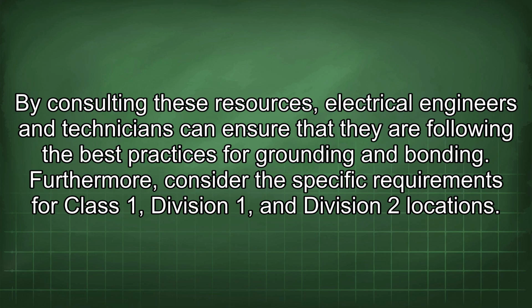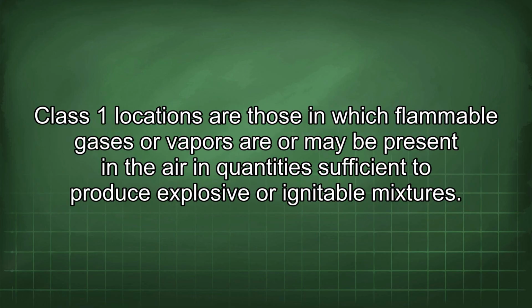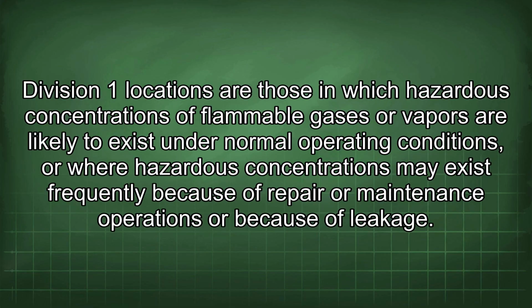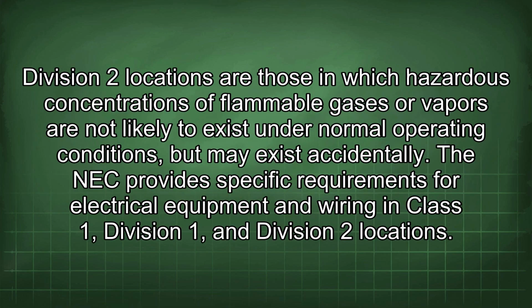Furthermore, consider the specific requirements for Class 1, Division 1, and Division 2 locations. Class 1 locations are those in which flammable gases or vapors are or may be present in the air in quantities sufficient to produce explosive or ignitable mixtures. Division 1 locations are those in which hazardous concentrations of flammable gases or vapors are likely to exist under normal operating conditions, or where hazardous concentrations may exist frequently because of repair or maintenance operations or because of leakage. Division 2 locations are those in which hazardous concentrations of flammable gases or vapors are not likely to exist under normal operating conditions but may exist accidentally.